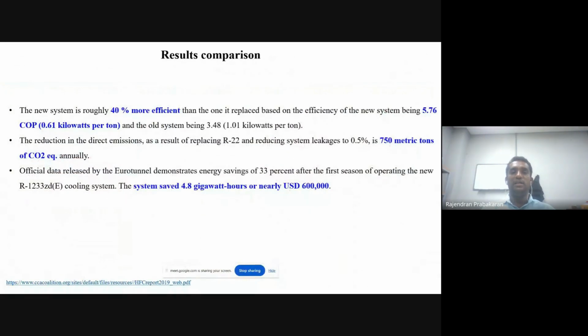This study indicates that after the first trial or first seasonal run, it was roughly 40% more efficient than the old one, and it has a COP of about 5.76, which was previously only about 3.5 for R22. It also only emits 750 metric tons of CO2 equivalent emissions. The official Eurotunnel data demonstrates an energy saving of a maximum of 32% compared to the old one, so it almost saved 4.8 gigawatt hours.